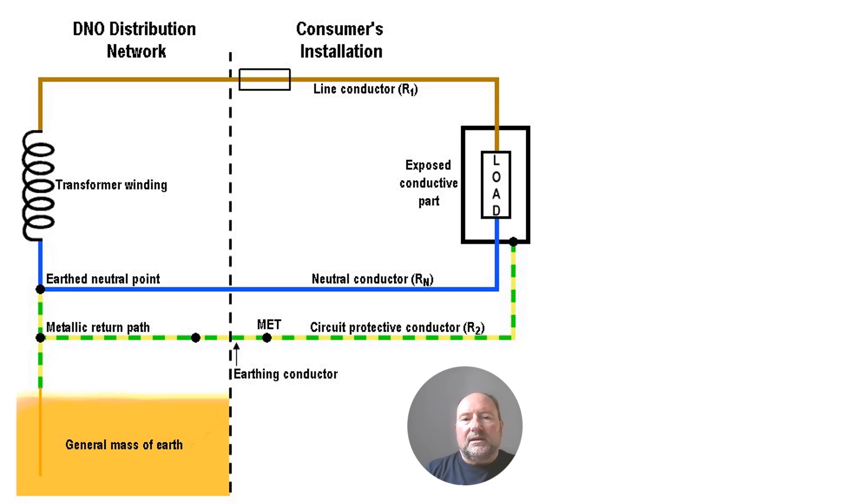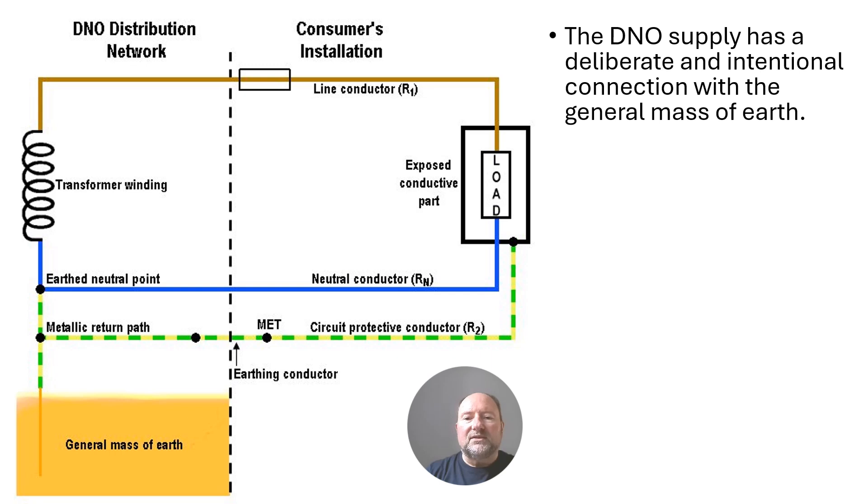Certainly in this country, the public distribution supply system has a deliberate and intentional connection to Earth. When I say Earth, I mean that general mass of Earth and that connection is made there at the Earthed neutral point of DNO secondary winding.